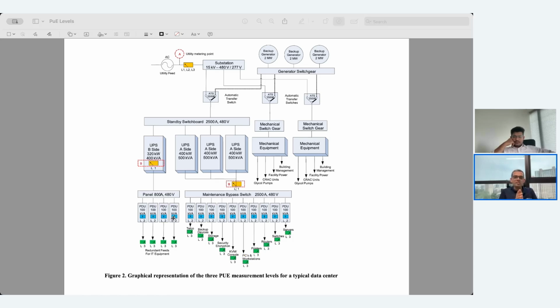Now, while we're talking about the location of the measurement of the PUE at these three different places, what is also very important is the measurement interval, or the frequency of measurement. So at a level 1 basic, one would expect at a minimum one reading at a monthly level, of your total DC energy and the UPS output. So that gives you a rough idea of where your PUE is sitting.